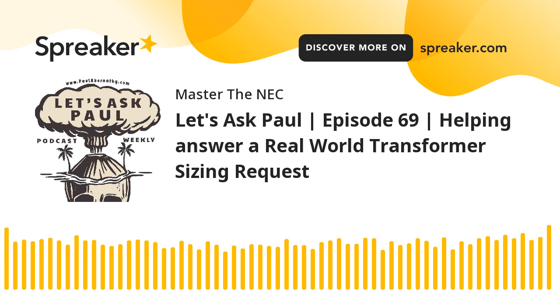It says a set of conductors feeding a single load or each set of conductors feeding separate loads shall be permitted to be connected to the transformer secondary without overcurrent protection at the secondary as specified in 240.21(C)(1) through (C)(6). Section 240.4(B) shall not be permitted for transformer secondary conductors. So what that means is if they don't correspond, you can't jump up to the next size. You with me? You get me?